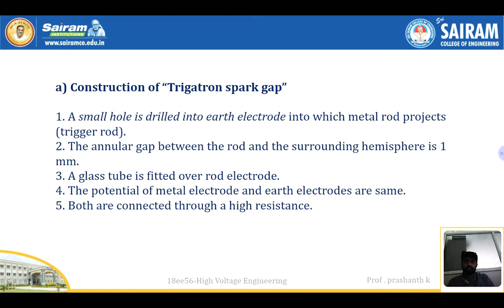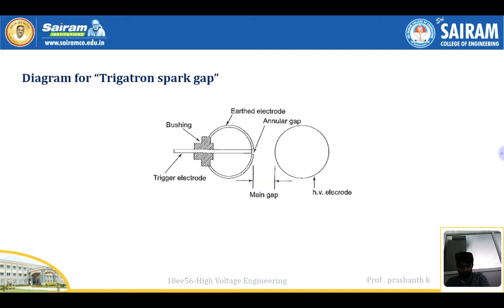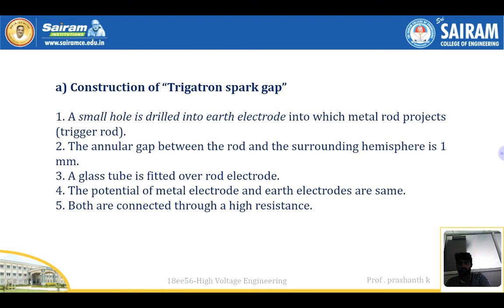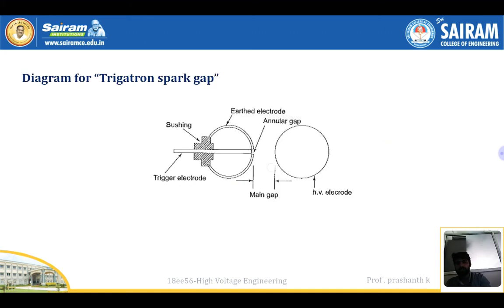Construction of a trigatron spark gap. A small hole is drilled into the earth electrode, into which a small metal rod is projected, the trigger rod. See here, there will be an annular gap, a small gap. The annular gap between the rod and the surrounding hemisphere is 1 millimeter. This part is 1 millimeter.